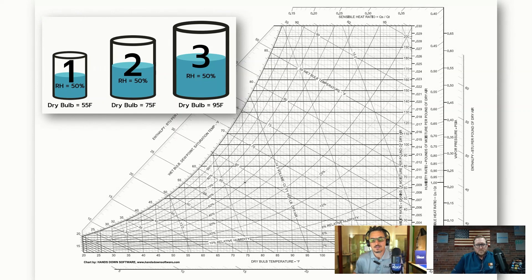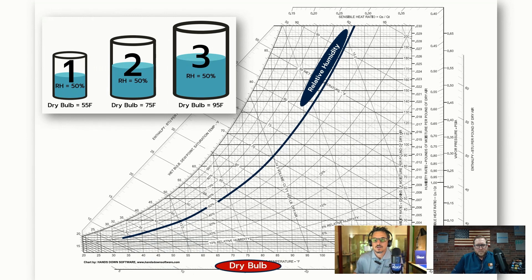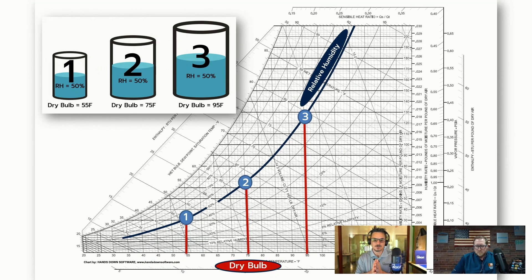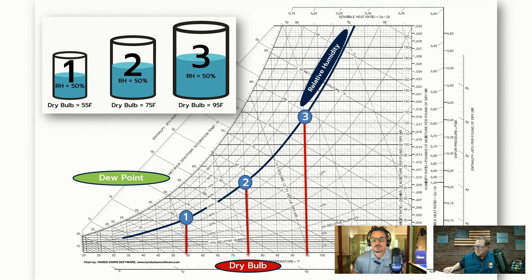We're going to illustrate that by plotting these on a psychrometric chart. We're going to take the 50% RH line, which is right here, and plot that against the dry bulb temperature of each of these containers. You'll see 55 degrees is here, 75 degrees is here, and 95 degrees is here. We'll put a little dot here to represent these containers. If you're familiar with psychrometrics — as we move up the chart, that's an increase in humidity, the actual amount of moisture in the air. You can see container three is much higher than one, of course, as we discussed.